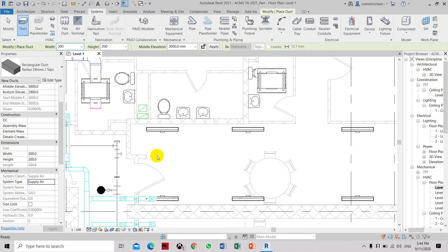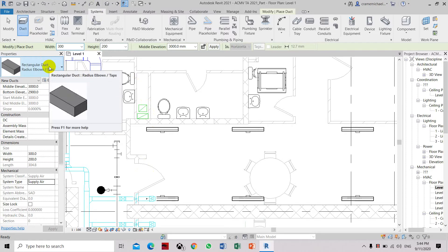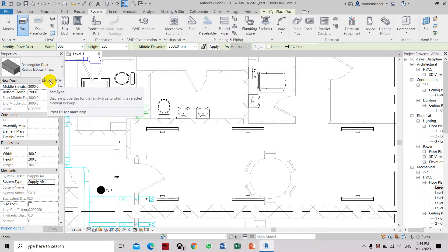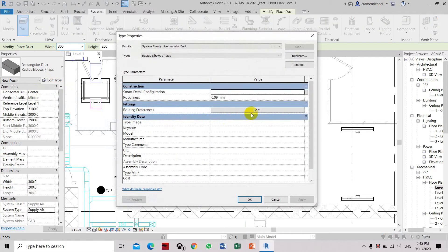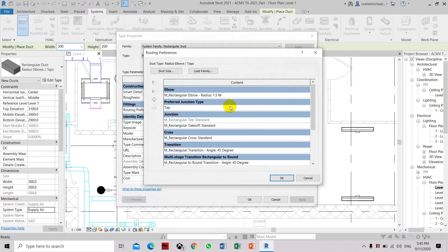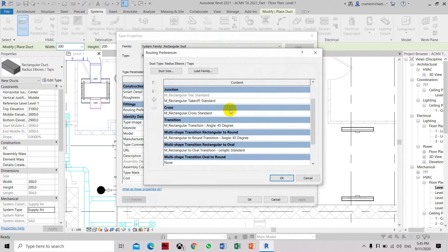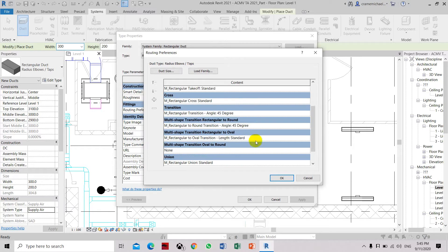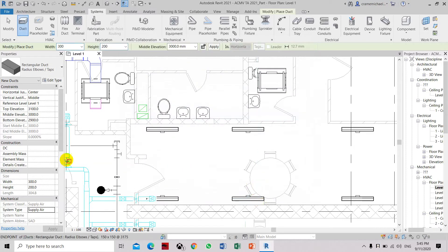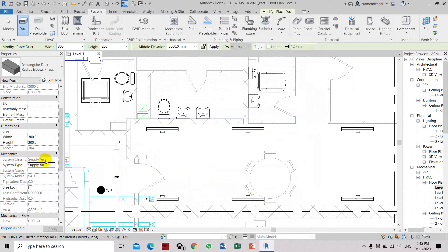We will now proceed to draw the supply air duct and return air duct. Go to System, Duct, and we will be using rectangular duct for this system. You can set the type of fittings you would like to use by clicking Edit, then select Routing Preferences — you can see there are different types of fittings available. I have already set my preferred fittings so I will leave it as is. Also check your system classification under Mechanical — it should be set to Supply, and the system type should also be Supply, since we are working on the supply air duct.